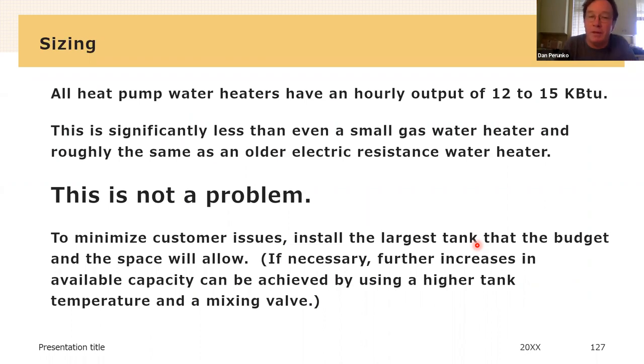We have a couple of available strategies. One is get the biggest tank that you can afford and the space will allow. If you need more capacity than that, you can raise the tank temperature to say 150 degrees and use a thing called a mixing valve to lower the delivered water temperature back down to 120. And so you're basically stretching the volume of the tank because you take less hot water out every time you use hot water in the house.